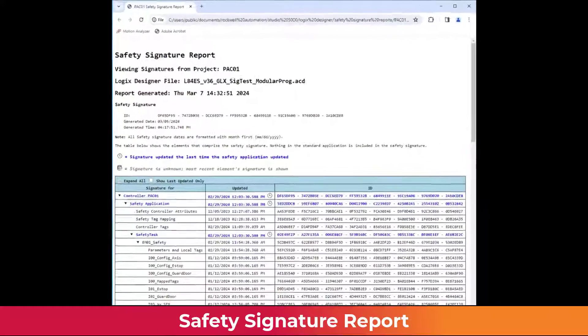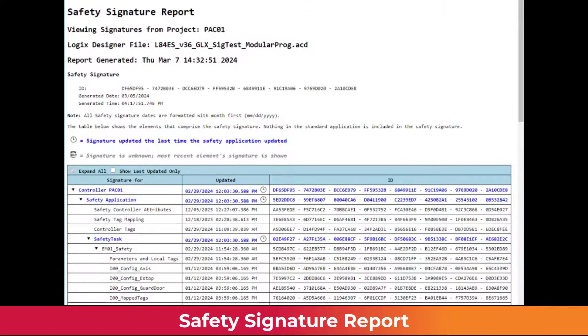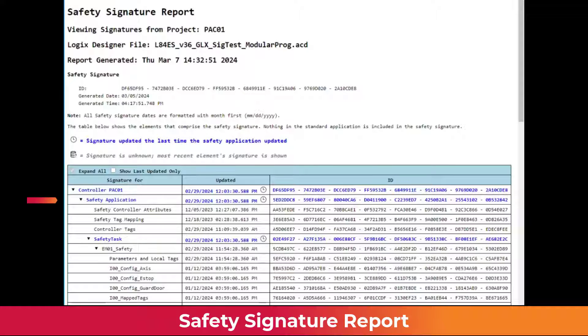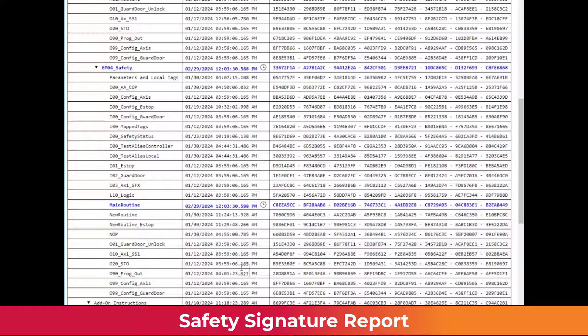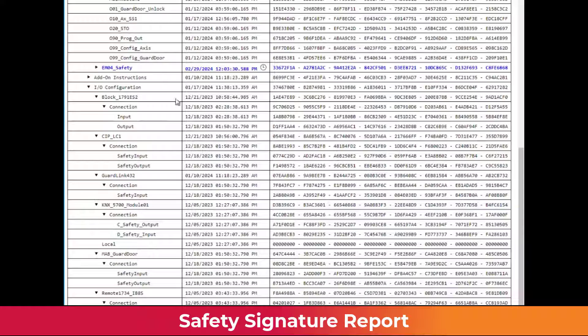A signature report HTM file for the current application is created locally and automatically opened in a web browser. The Safety Signature report contains project file information, the report generated date, the controller safety signature, and all safety signature elements. The default view is Expand All, but the report can be collapsed by element sections or filtered to show only the last-updated blue items.